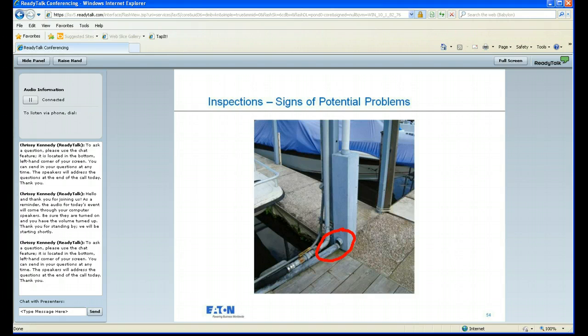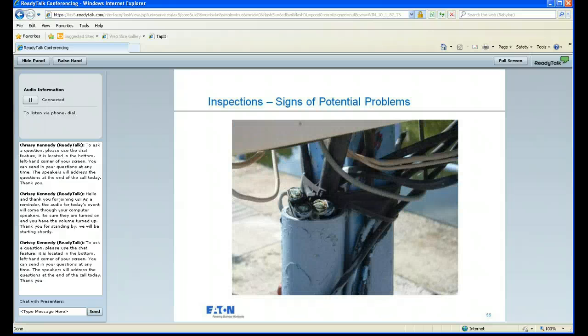Any sort of open conduits where you've got connection points that are open, this is where water can seep in and cause damage to your wires. That's another sign of something that needs to be taken care of. These conductors should either be capped off, cut off, or simply removed, just in case a circuit breaker is activated without the knowledge of someone out in the marina. If someone walked up to this and touched it, that could lead to a very serious issue.